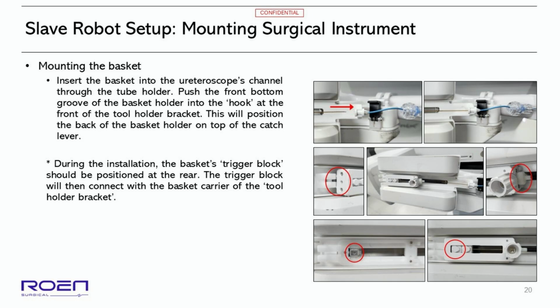Insert the basket into the ureteroscope's channel through the tube holder. Push the front bottom groove of the basket holder into the hook at the front of the tool holder bracket. This will position the back of the basket holder on top of the catch lever. During the installation, the basket's trigger block should be positioned at the rear. The trigger block will then connect with the basket carrier of the tool holder bracket.